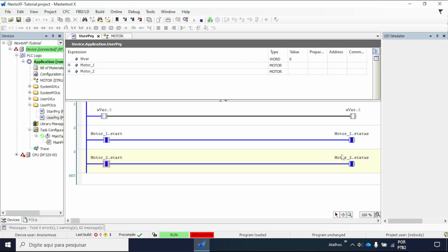The main advantage of this approach is project organization and scalability. For example, if you have 20 motors and each motor requires 4 standard variables, you would normally need to create 80 individual variables. With a custom data type, you only need the 4 variables once inside the motor type and then simply declare 20 variables of type motor. Each motor automatically contains all of the standard variables defined in the structure. This greatly simplifies project development, improves our organization, and makes maintenance much easier as the project grows.